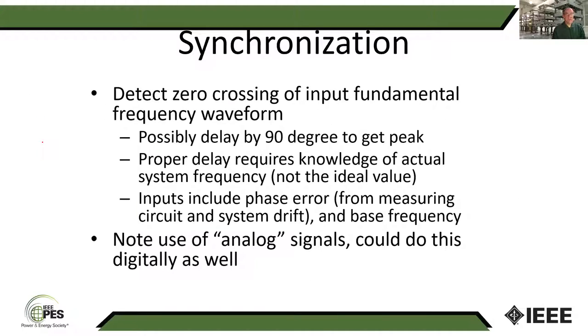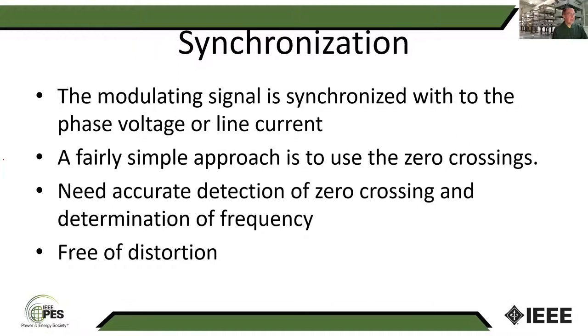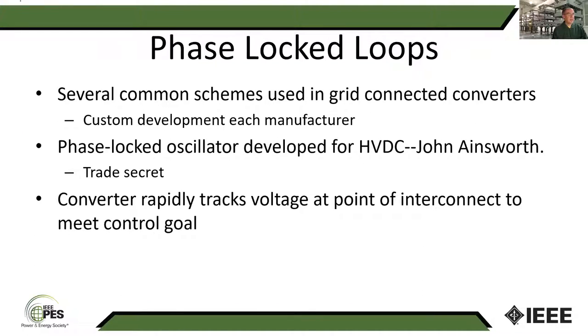And then for synchronization, as I mentioned, they need to have some way of tracking the power system frequency. And so the most common way they do this is some sort of a PI controller that's based on what's called a phase lock loop. And this actually goes back to HVDC converters in the 1960s, when what was then the English Electric Company, which eventually became Alstom and is now part of GE, developed this for HVDC converters.